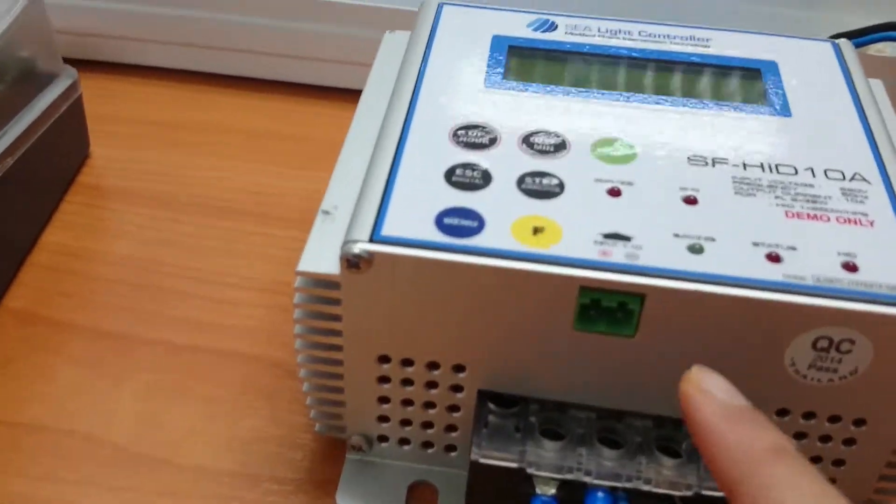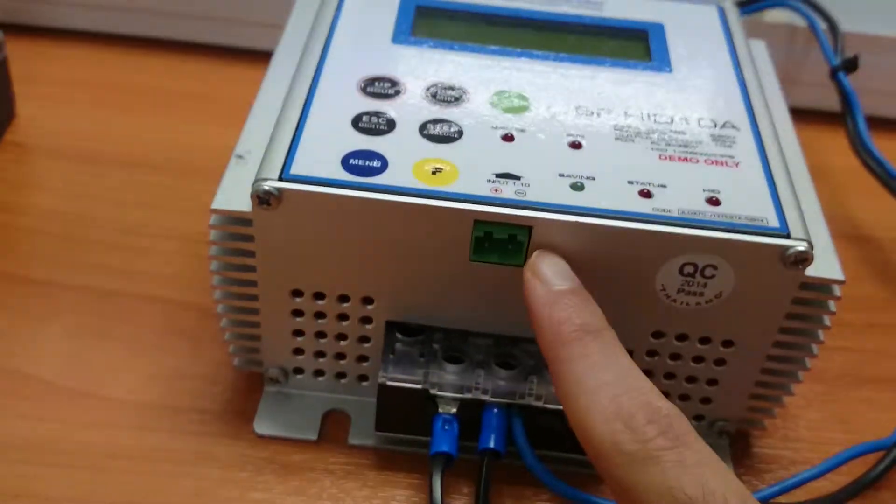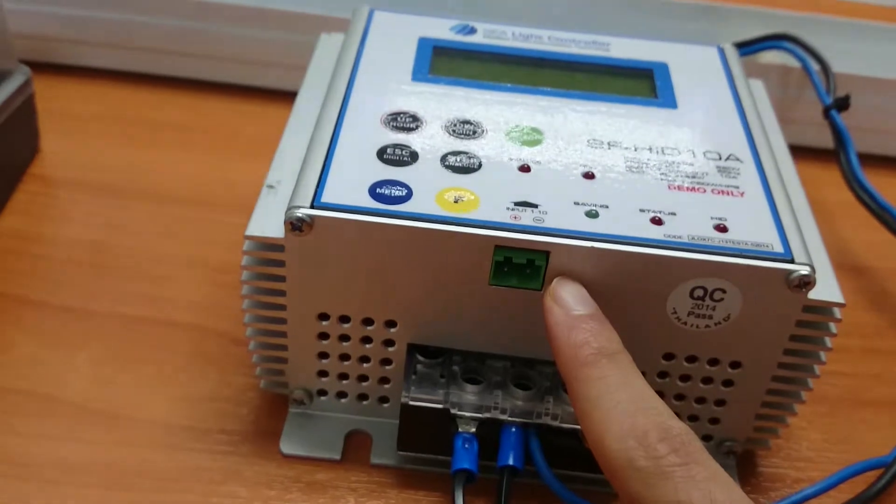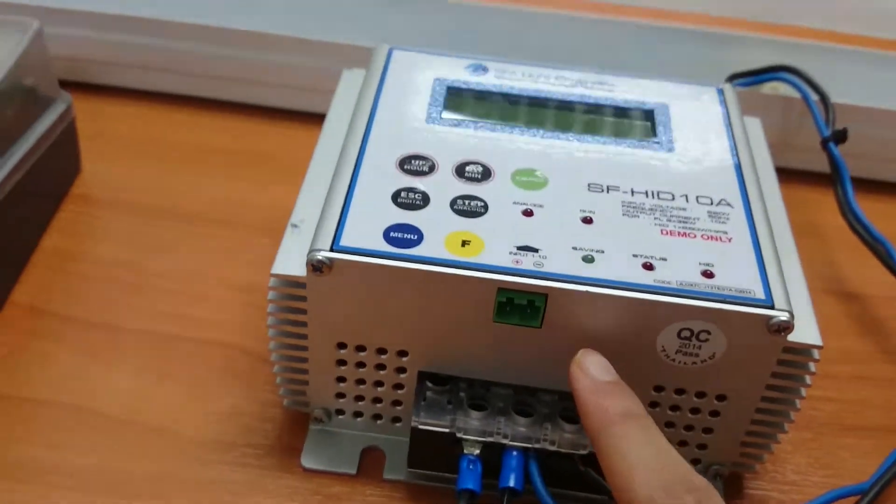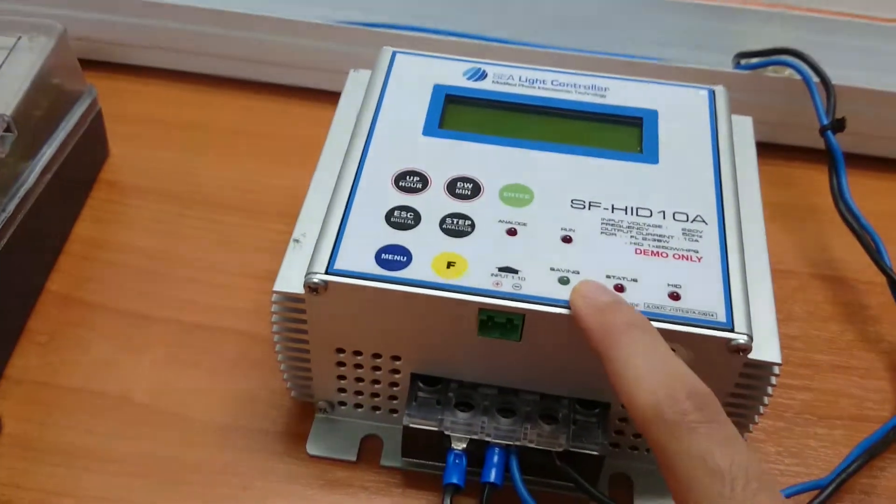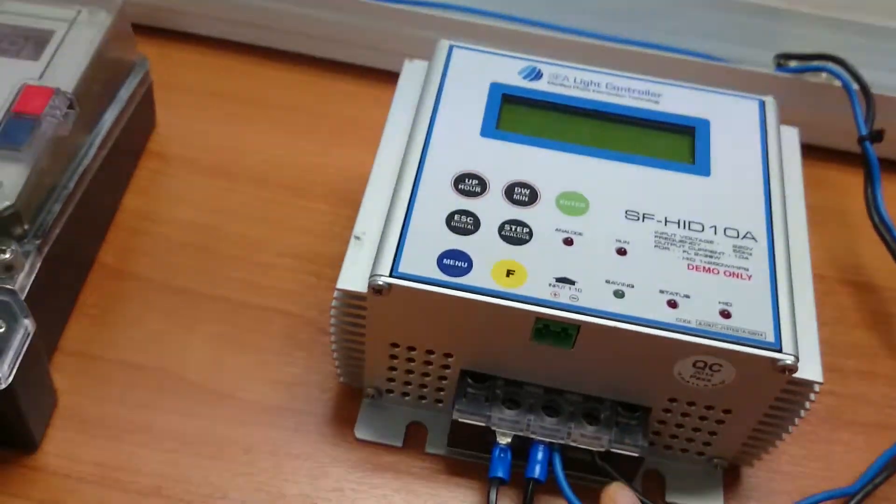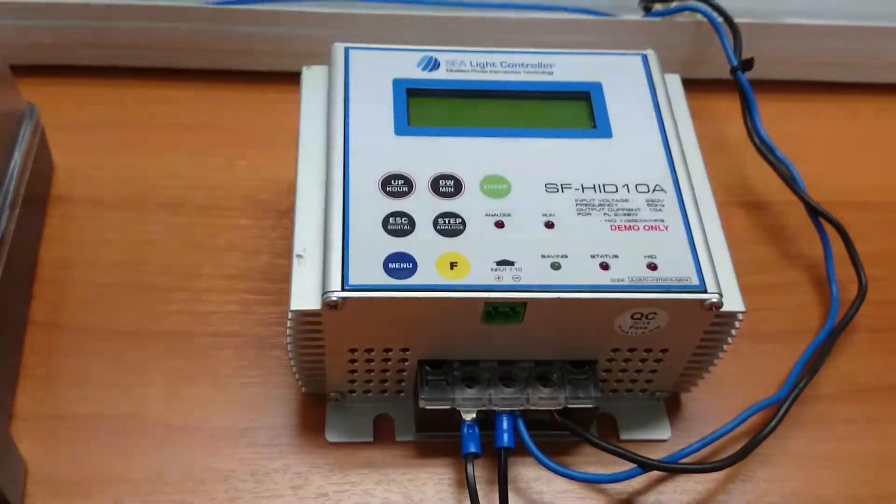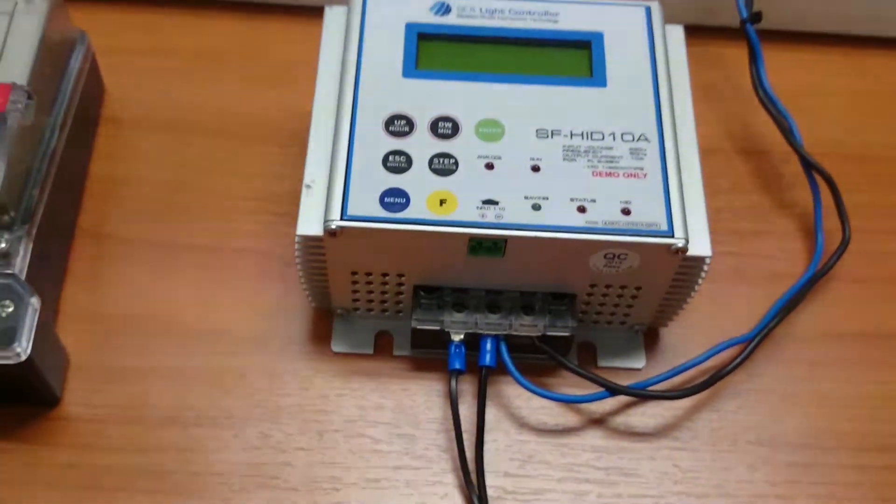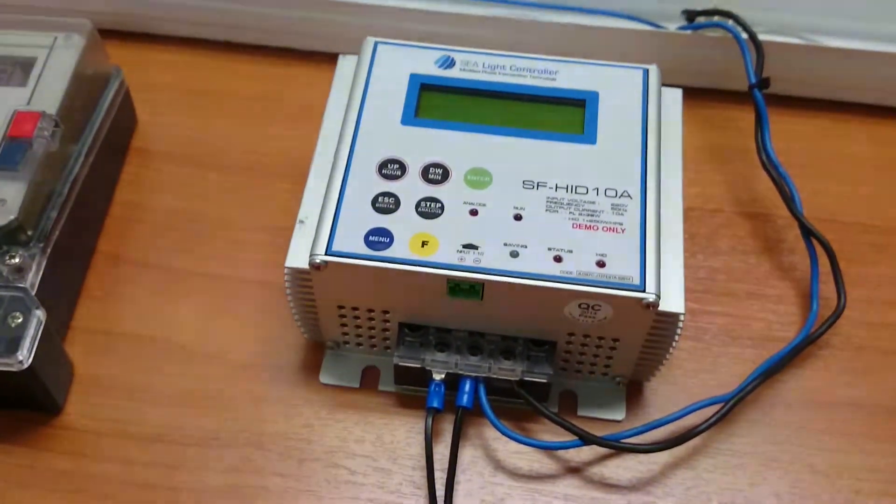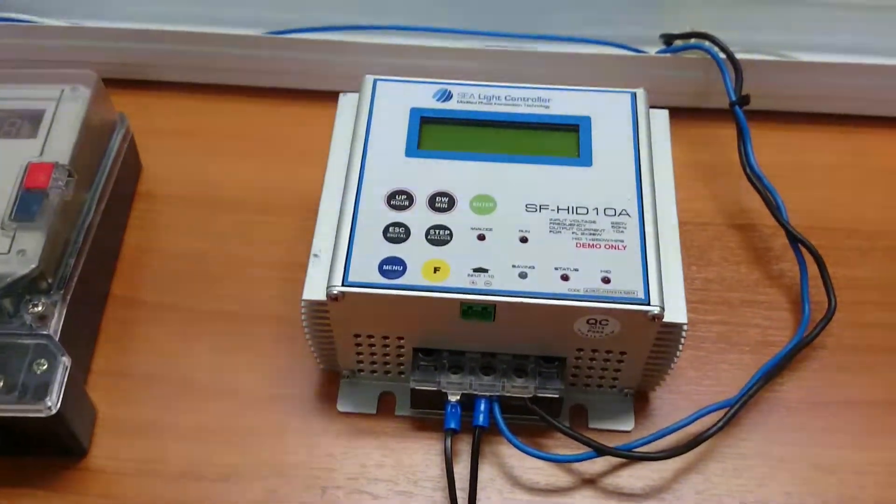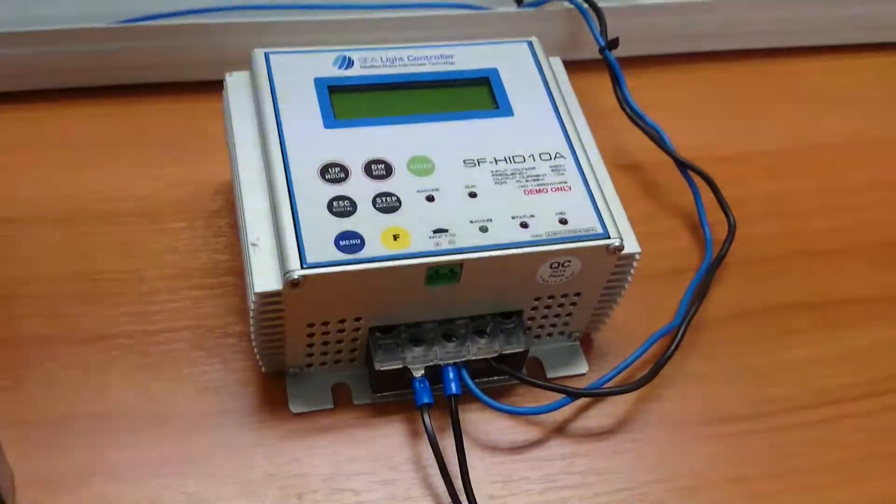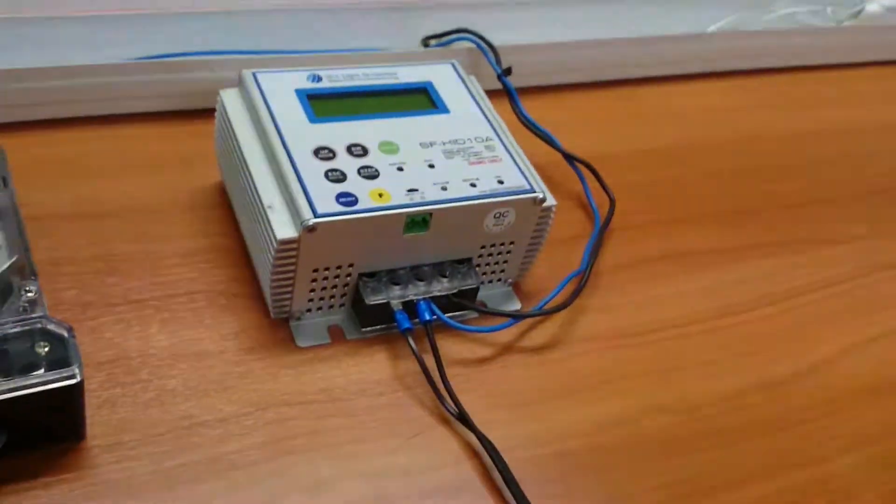We have the 0 to 10 volt port over here. If you have your own external device that you would like to use for remotely operating the SEA Light Controller you can do so. If you input a 10 volt signal then it would operate at 100% power. If you input a 7 volt signal it would operate at 70% power and so on. The minimum that it can operate for fluorescent lights is 50% power.